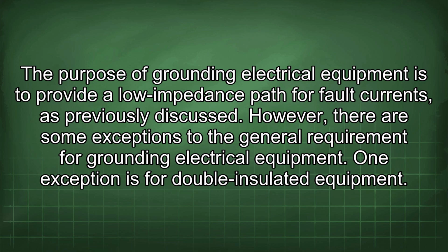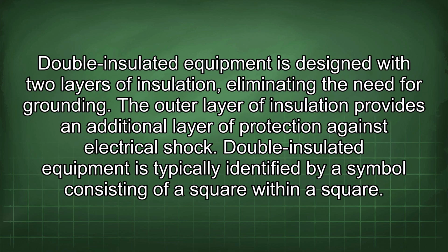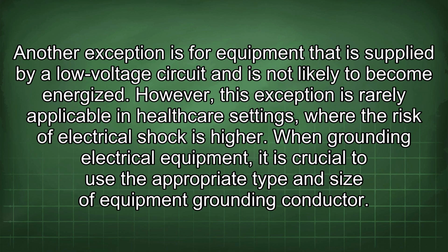One exception is for double insulated equipment. Double insulated equipment is designed with two layers of insulation, eliminating the need for grounding. The outer layer of insulation provides an additional layer of protection against electrical shock. Double insulated equipment is typically identified by a symbol consisting of a square within a square. Another exception is for equipment that is supplied by a low voltage circuit and is not likely to become energized. However, this exception is rarely applicable in healthcare settings where the risk of electrical shock is higher.